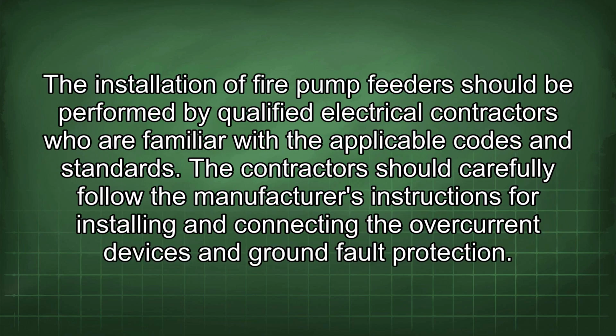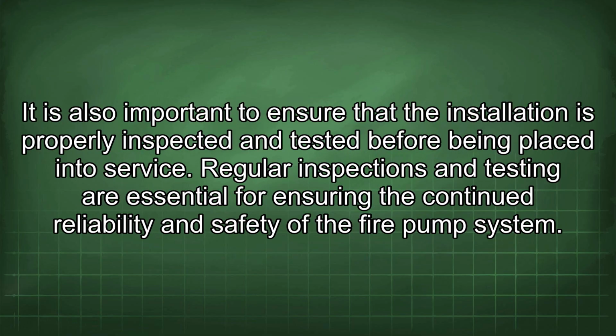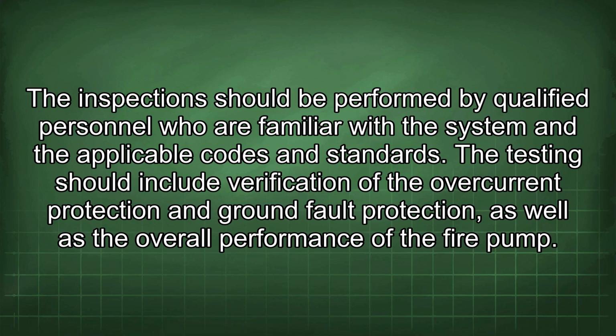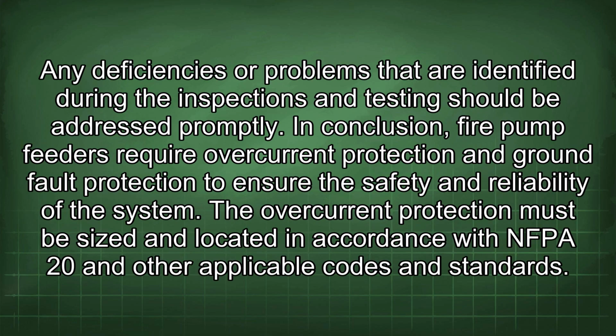The installation of fire pump feeders should be performed by qualified electrical contractors who are familiar with the applicable codes and standards. The contractor should carefully follow the manufacturer's instructions for installing and connecting the overcurrent devices and ground fault protection. It is also important to ensure that the installation is properly inspected and tested before being placed into service. Regular inspections and testing are essential for ensuring the continued reliability and safety of the fire pump system. The inspection should be performed by qualified personnel who are familiar with the system and the applicable codes and standards. The testing should include verification of the overcurrent protection and ground fault protection, as well as the overall performance of the fire pump. Any deficiencies or problems that are identified during the inspections and testing should be addressed promptly.